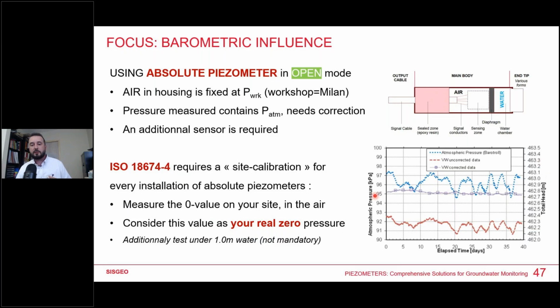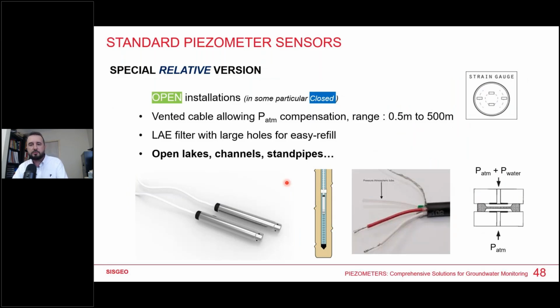Even the norm, the ISO standard, requires a site calibration for every installation of absolute piezometers. For that, it's very simple. You take your sensor in the air and then you measure the zero value. So inside the air, this is your real zero value at your site, because depending on the altitude and depending on the weather, you will have some differences from the zero that is stated inside the calibration sheet. Then I hope you understood this principle, because then we have a special version, which is the relative version.